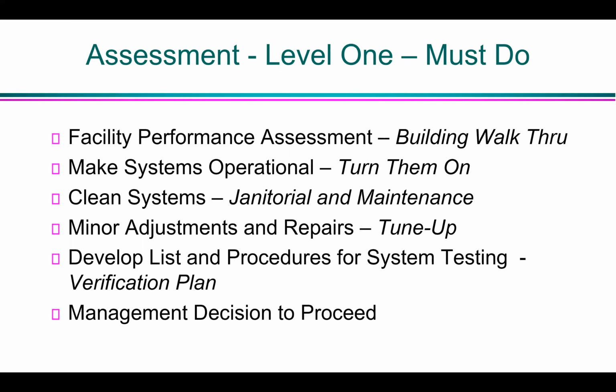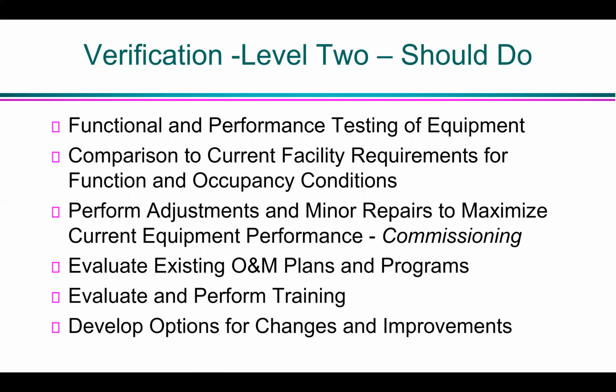Figure out what you need to test. Some things are working fine; others, like outside air units or cooling towers, may not be working as well, or you don't know exactly how they're performing. So you need a plan to verify that performance, then find out from the owner or manager what they want to do and how far they want to go. The next part talks about the verification stage - these are things you should do.